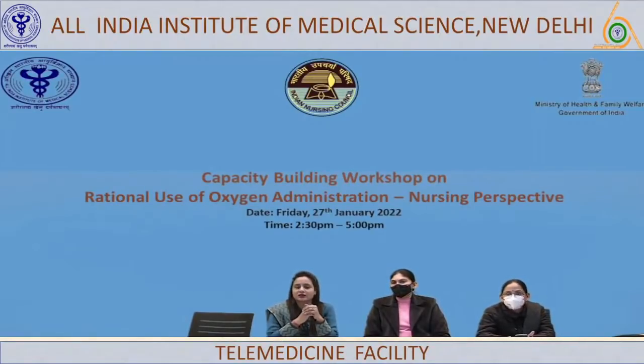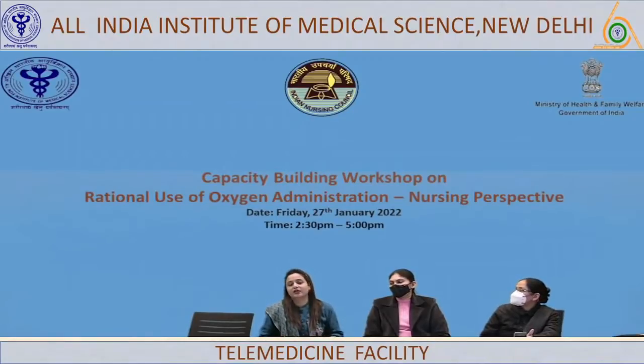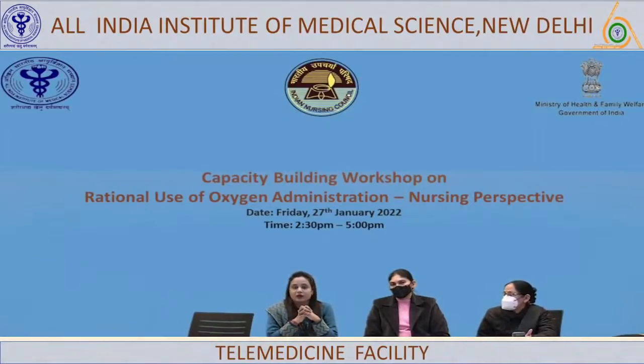Then coming to the external surfaces of the ventilator, we need to clean them first with soap and detergent, making sure that we use a minimum amount of water, as this is an electrical appliance and we may ruin it by applying too much water. Electrical circuits need to be considered. They should be kept away from the water which we are using. Then we have to dry them with a dry cloth, and then disinfect them with a compatible disinfectant. Now, what do we mean by compatible disinfectant? Most of the time, the device manufacturer provides a guideline on how our ventilator needs to be disinfected, so we can use that. Otherwise, in hospital settings, we use ethanol 70 to 90%, hydrogen peroxide or sodium hypochlorite to disinfect these ventilators.